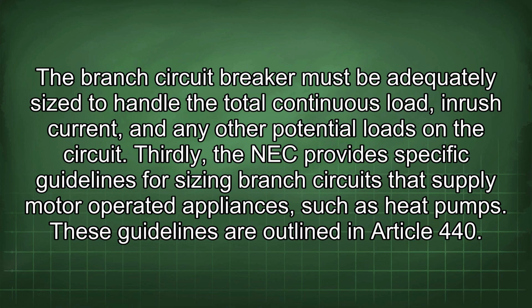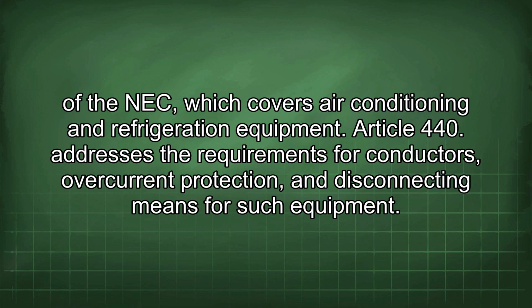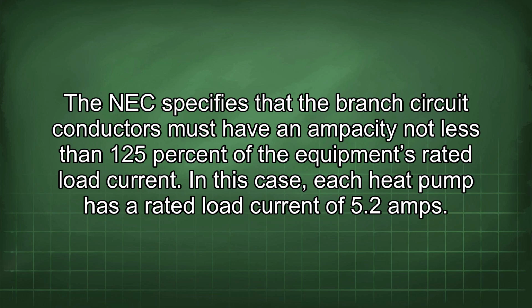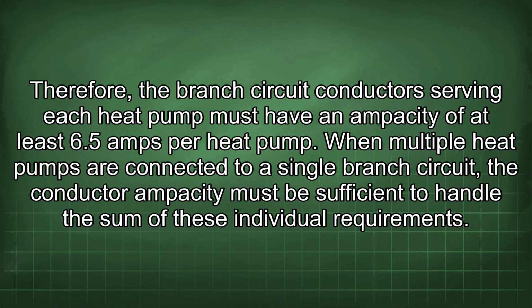Thirdly, the NEC provides specific guidelines for sizing branch circuits that supply motor-operated appliances such as heat pumps. These guidelines are outlined in Article 440 of the NEC, which covers air conditioning and refrigeration equipment. Article 440 addresses the requirements for conductors, overcurrent protection, and disconnecting means for such equipment. The NEC specifies that the branch circuit conductors must have an ampacity not less than 125% of the equipment's rated load current. In this case, each heat pump has a rated load current of 5.2 amps. Therefore, the branch circuit conductors serving each heat pump must have an ampacity of at least 6.5 amps per heat pump. When multiple heat pumps are connected to a single branch circuit, the conductor ampacity must be sufficient to handle the sum of these individual requirements.